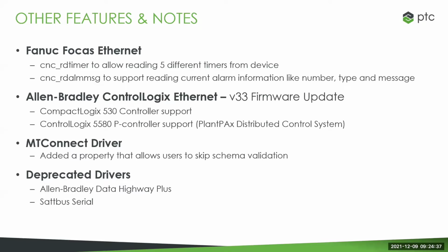And for the MTConnect driver, for those who are in the machine shops using the MTConnect driver, we now offer you a capability to actually skip the schema validation. For those who are familiar with MTConnect, the payload that they usually use between the MTConnect drivers is the XML file. Sometimes the machine that you are interfacing to, for some reason, the XML has maybe a typo or was developed in a way that doesn't really conform to the proper schema. So now we have a capability for you to ignore that schema validation. We can ignore that it's not a properly formed schema, and we just continue to pass that message.